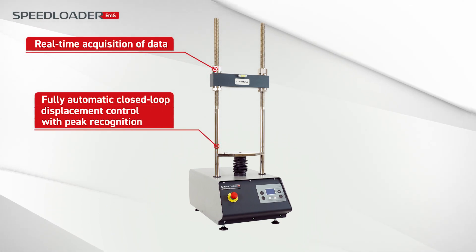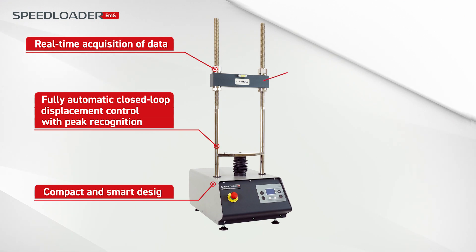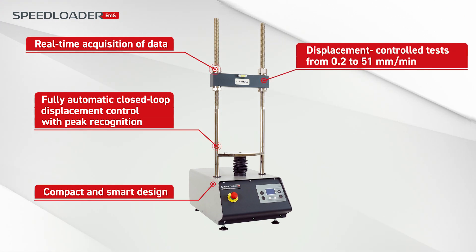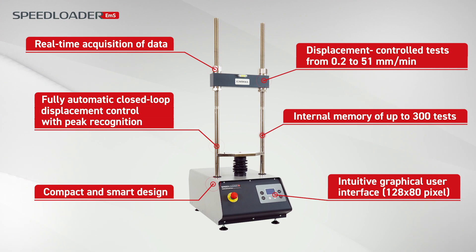Testing is efficient with fully automatic real-time acquisition of load and displacement data and peak recognition. You can set up testing speeds easily from 0.2 to 51 millimeter per minute and send all test results to your computer via serial port or store them in internal memory.